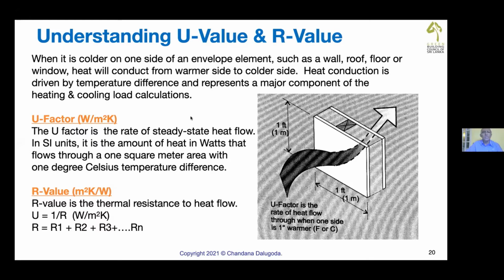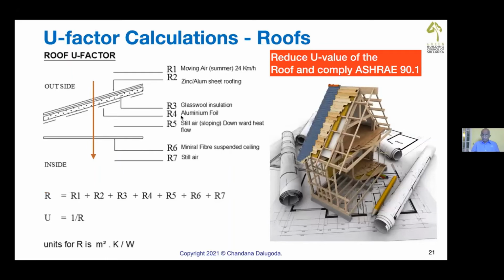This is how engineers find the U factor for a roof, the entire construction, mind you. Now here the U factor comprises a roof and then an attic and then a drop ceiling. You can see a roof structure and then an attic space and then a ceiling. So we calculate the U factor for the entire structure and compare with the ASHRAE values and try to reduce the heat flow.